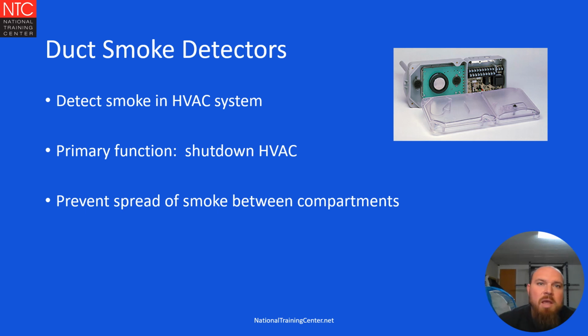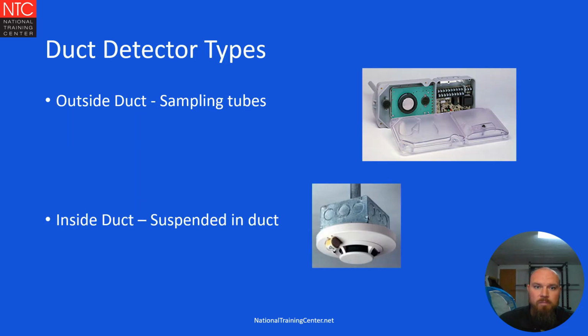Duct detectors can be a frustrating device to work with, so let's take 2 minutes to learn a little bit more about them. So what a duct detector does is it's there to detect smoke within the HVAC system. The primary purpose of your duct detector is to shut off the HVAC unit once it's been activated. In doing this, it is going to prevent the spread of smoke between compartments throughout the entirety of the building, which is then going to enhance the life safety of the occupants of the building.